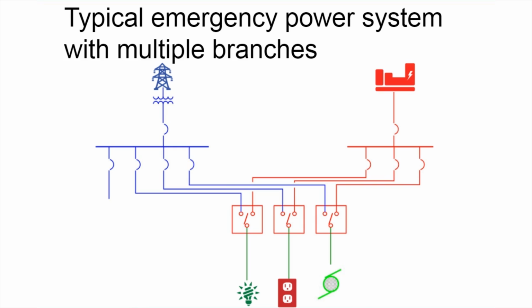We can start building upon this system by adding more transfer switches. Now we'd have all of our life safety loads fed off of one transfer switch, and we could have optional loads fed off of another, and, as in a healthcare environment, critical loads fed off of another one. And if some are good, does that make more better? Not always. It's also known as putting all your eggs in one basket. This can cut both ways.